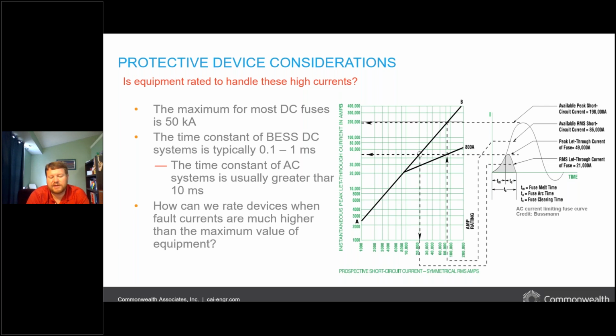Now, generally, current limiting fuses are based on AC time constants, usually in the 10 millisecond range. However, the DC fault current rise is very, very fast, generally on the order of 0.1 to 1 millisecond. So that's one to two orders of magnitude faster than our typical AC systems. That's the main challenge: making sure that we understand what this race is.